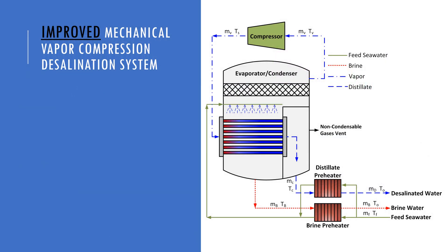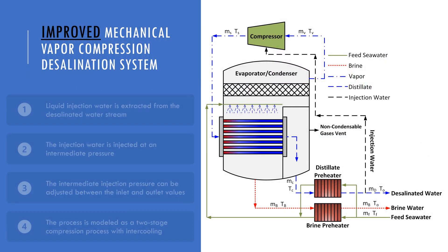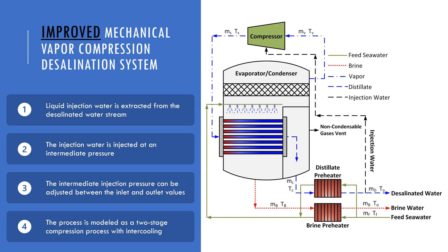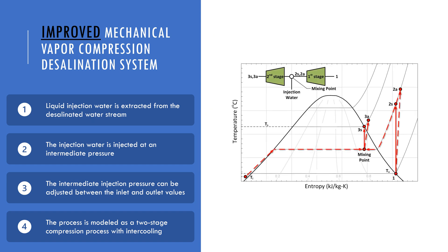In our improved system, a water injection line is extracted from the desalinated water stream to be injected into the compressor at an intermediate pressure. The intermediate injection pressure can be adjusted between the inlet and outlet values. The injection process is modeled as a two-stage compression process with intercooling at an intermediate pressure. However, if the injection is done at the inlet pressure, it means we have a single-stage compression with a two-phase inlet vapor. For other injection pressure values, the process is a two-stage compression with intercooling.